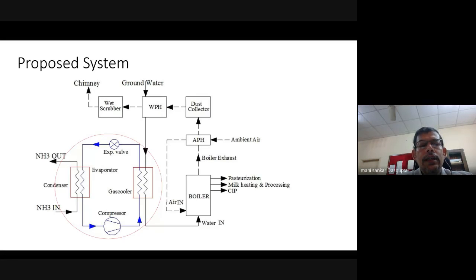What it does is the groundwater is heated in the WPH unit, and then before going into the boiler, it is further heated by the heat exhausted from the condenser of the NH3 unit. So this side is used as an evaporator for the CO2 unit, and then as a gas cooler which transfers the heat to the water.